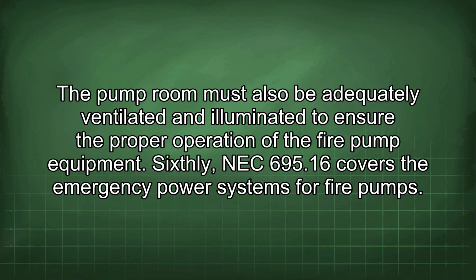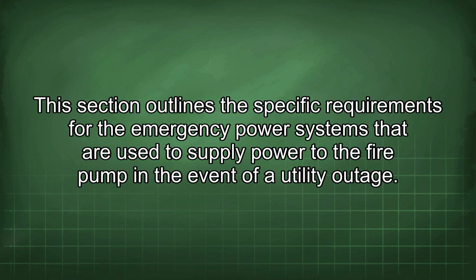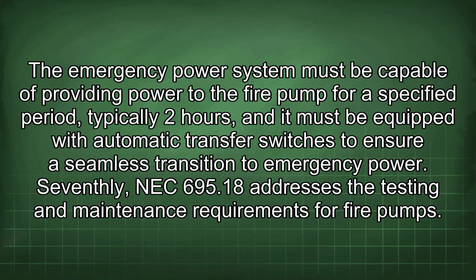695.16 covers the emergency power systems for fire pumps. This section outlines the specific requirements for the emergency power systems that are used to supply power to the fire pump in the event of a utility outage. The emergency power system must be capable of providing power to the fire pump for a specified period, typically 2 hours, and it must be equipped with automatic transfer switches to ensure a seamless transition to emergency power.